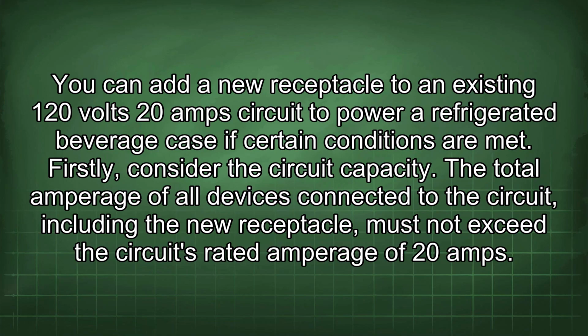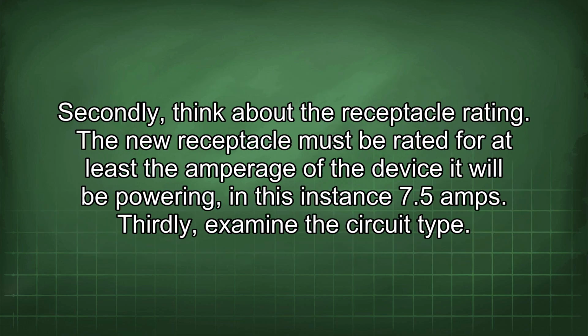You can add a new receptacle to an existing 120 volts 20 amp circuit to power a refrigerated beverage case if certain conditions are met. Firstly, consider the circuit capacity. The total amperage of all devices connected to the circuit, including the new receptacle, must not exceed the circuit's rated amperage of 20 amps. Secondly, think about the receptacle rating.